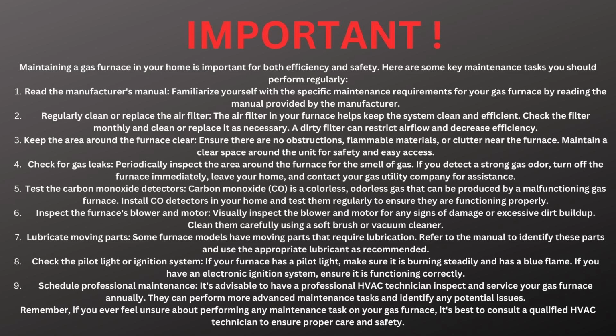If you have what I call a steel filter or a cleanable type filter, it's kind of made of a metal mesh. You have to take it out and you clean it and wash it out regularly. Those are okay. They can restrict air a little bit, but I've seen many of them out there. I recommend pleated filters over any filter out there. A pleated filter is good for people who have allergy issues. It kind of helps with that. It also collects 90% of the dust and debris that comes in there. Those standard cheap ones that have the metal circle rings that are cut out on them, they collect about 10-15%. They're just awful. Those are cheap throwaways, and they do you no good. Get a good pleated filter, a 3M, or one that's equivalent.